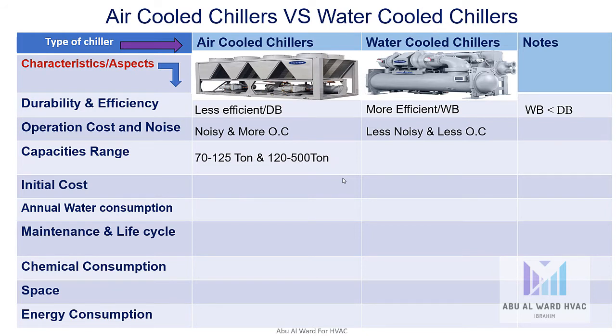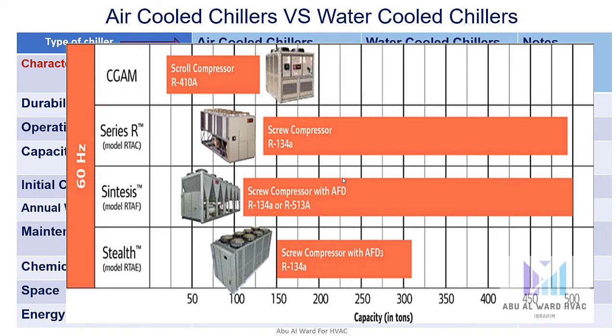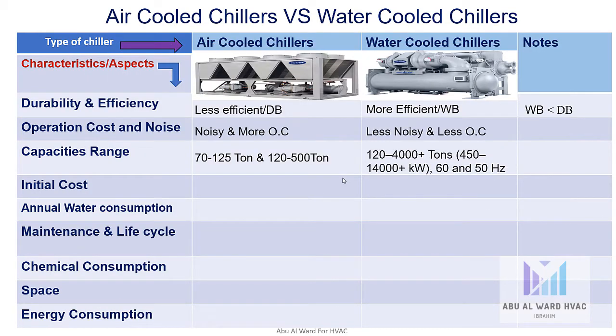Capacity range. The air-cooled has two categories, from 70 to 125 tons and from 120 to 500 tons for some of the centrifugal and screw chillers. As we see here in this screw compressor chillers series, we have some manufacturers with range starting from less than 50 reaching to 500. Water-cooled chillers, the range is between 120 to 4,000 tons. That means 450 to 14,000 kilowatt, which is a larger range than the air-cooled chillers.